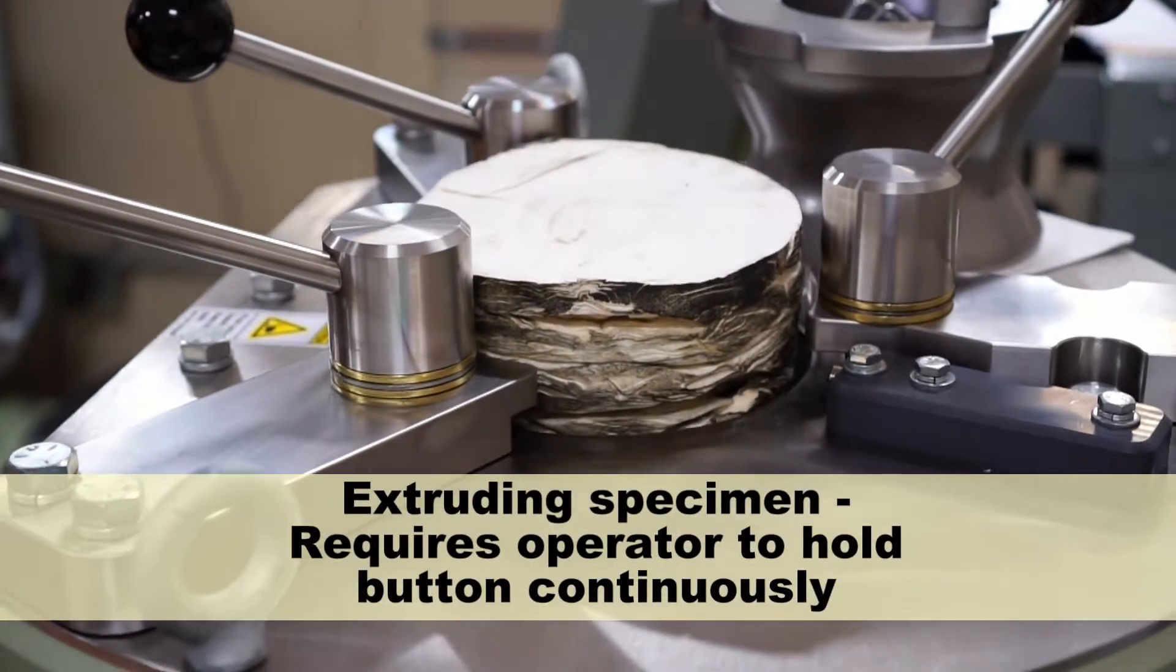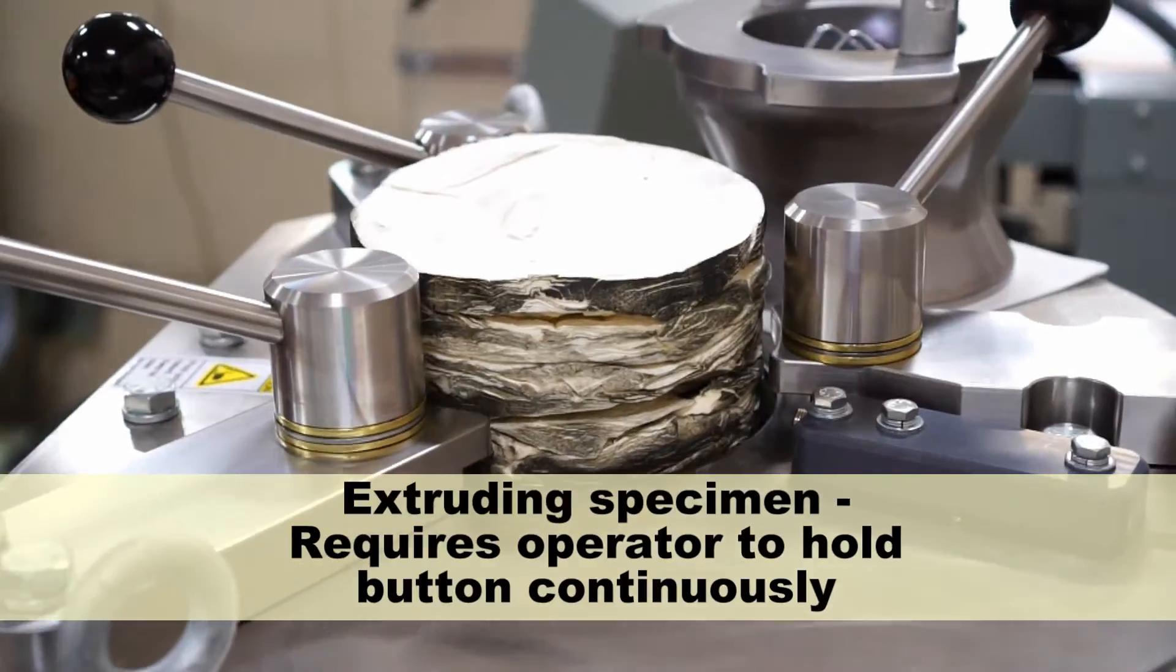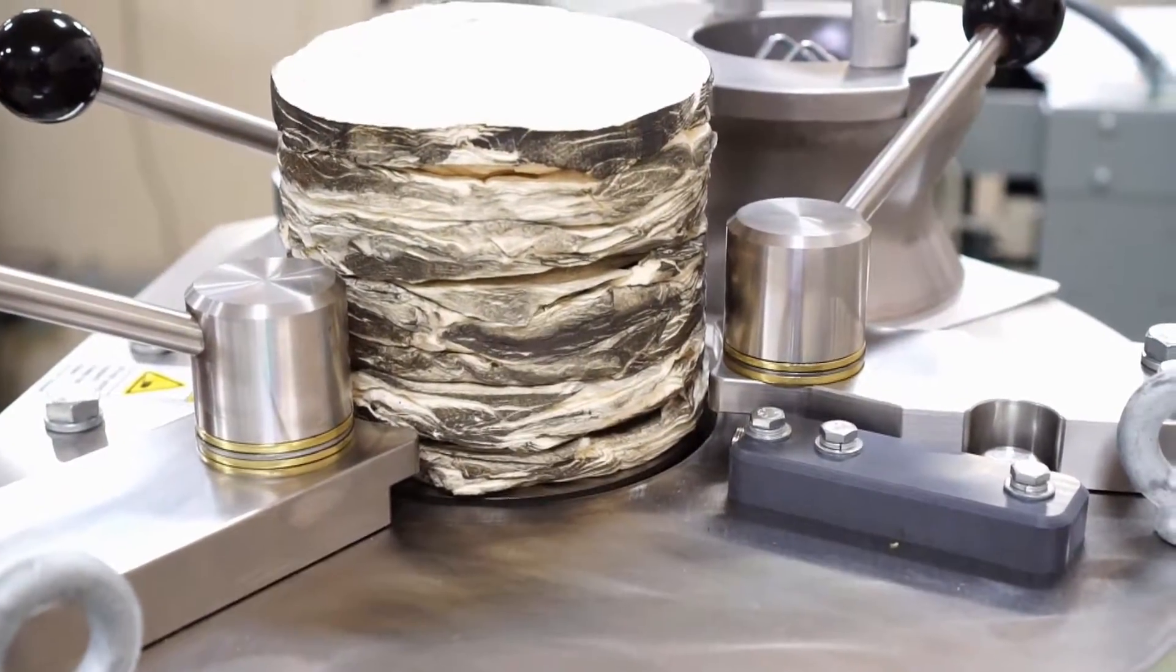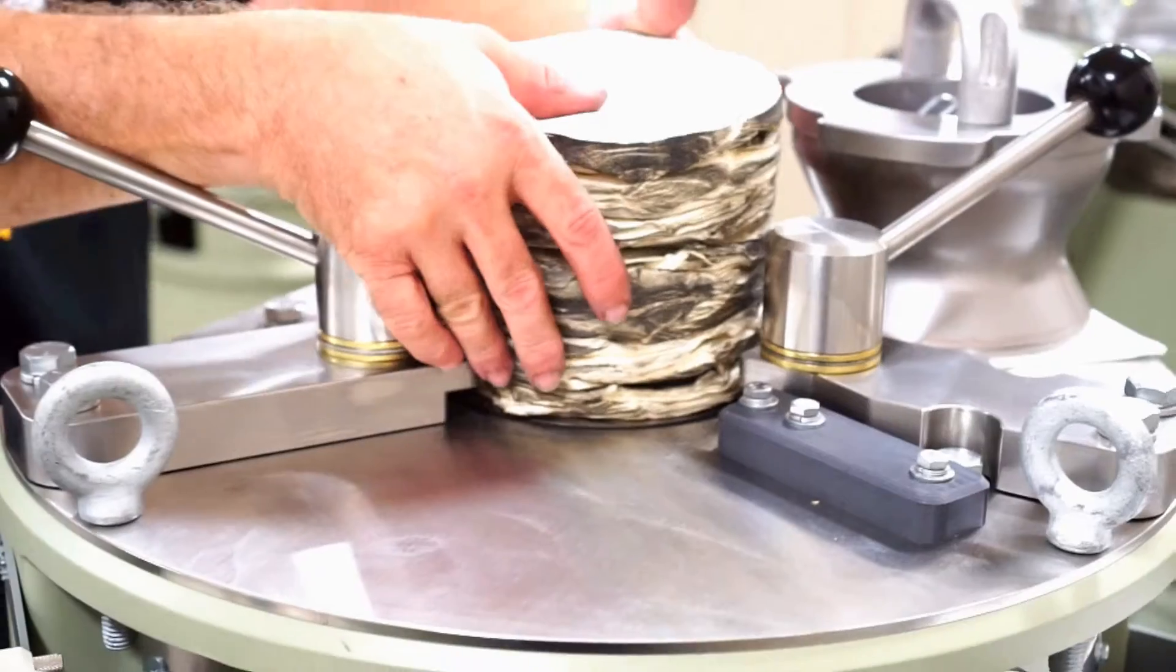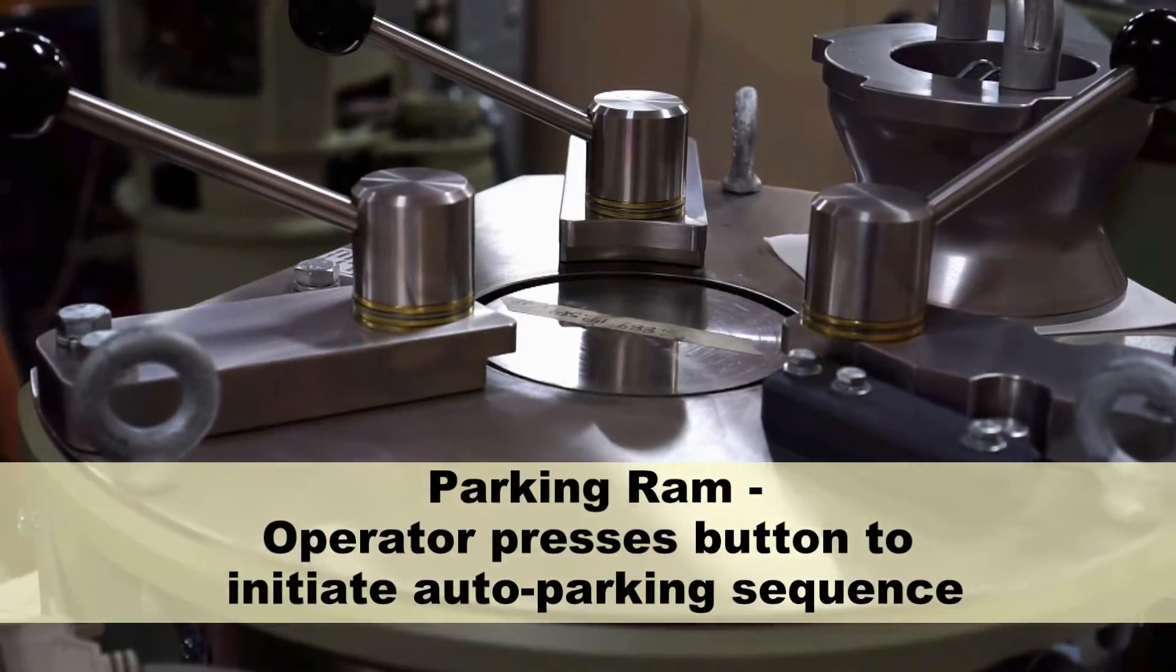The specimen is extruded from the mold by pressing and holding the up button. If the operator releases the button, the machine motion will stop immediately. The specimen is pressed out of the mold and emerges from the top of the machine. When the specimen has been fully extruded, it is removed and set aside.